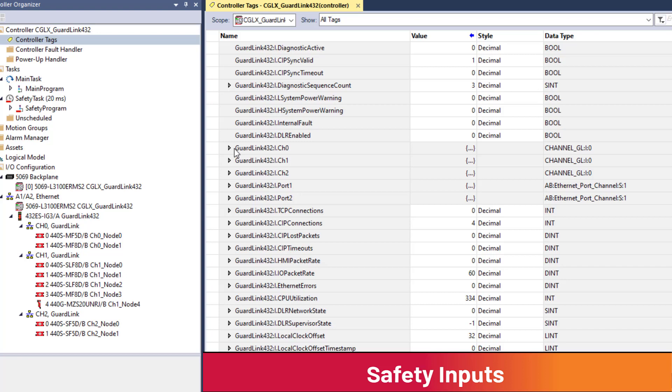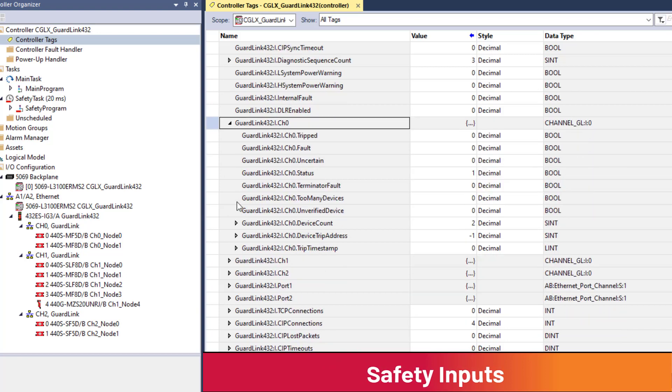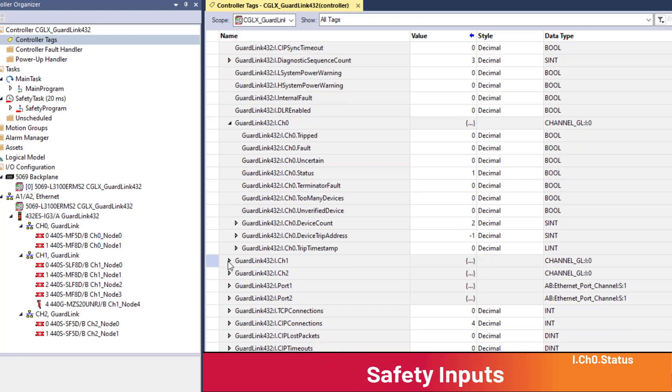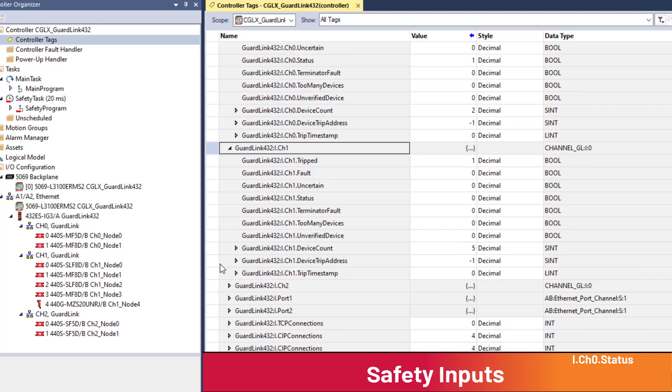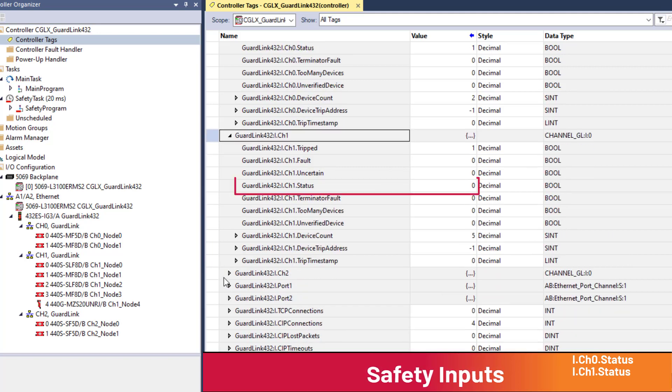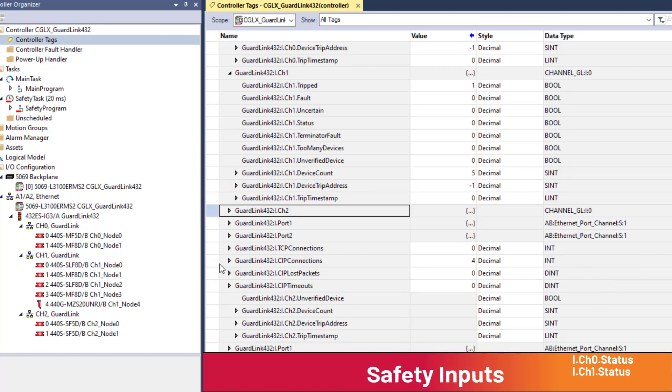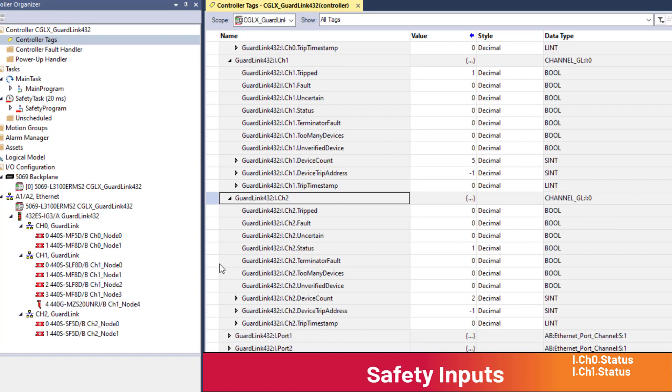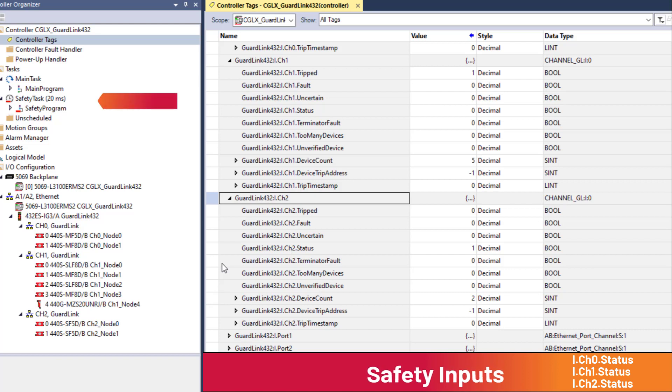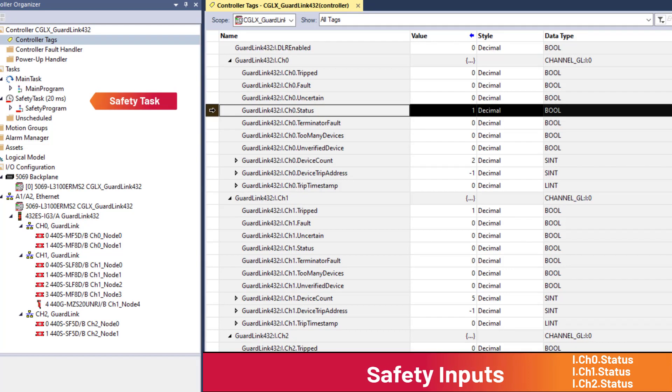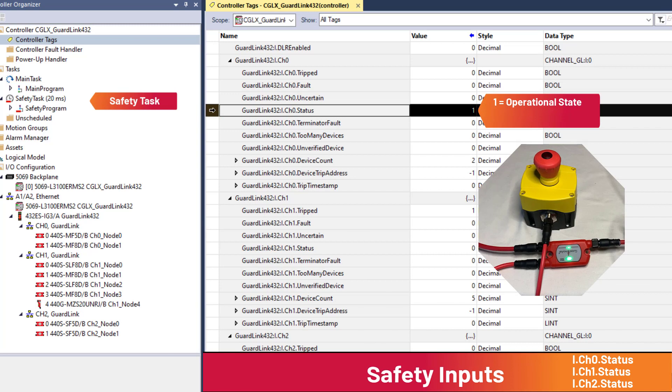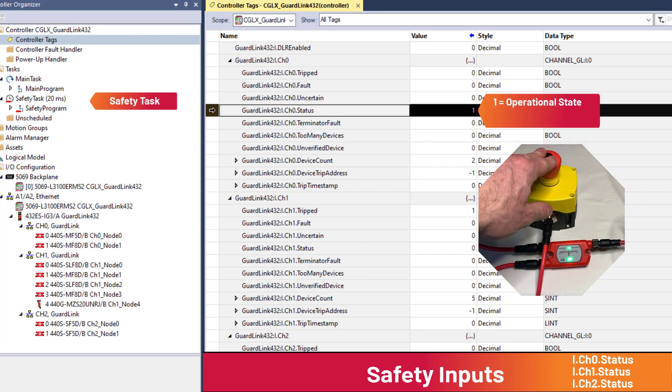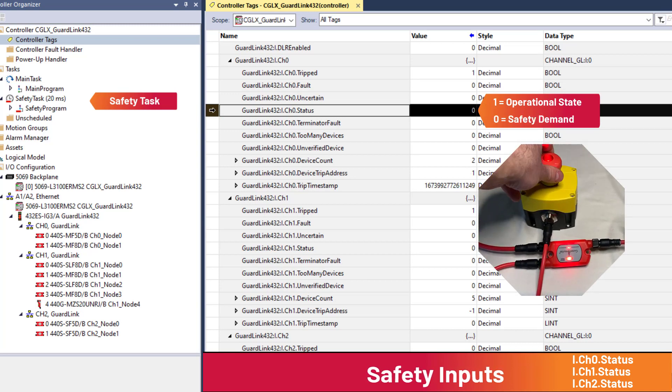Very important to note are the three safety rated input tags: channel 0 status, channel 1 status, and channel 2 status. The status tags for each GuardLink channel can be used in the GuardLogix safety task to indicate whether an individual GuardLink channel has a safety demand. 1 means no safety demand, typically safety is run ready. 0 means safety demand, typically a safe stop request.